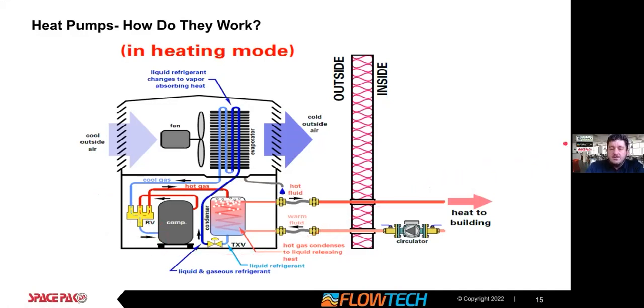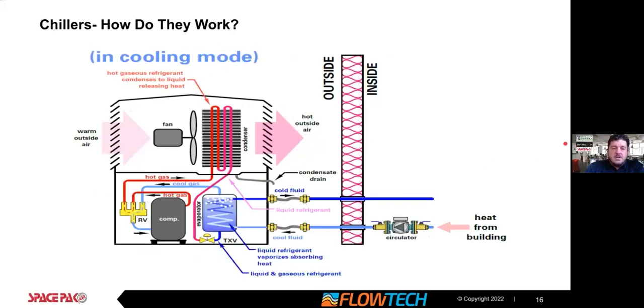So in the summertime, it'll go into cooling mode and it operates in the opposite direction. And you're running compressed refrigerant over a coil and gathering some cooling energy, even though it might be warm outside. You're able to gather some cool energy to chill water and circulate chilled water to and from that buffer tank. We'll get into glycol percentages and some other design criteria, but this is an overview of kind of what's going on in the box, so to speak.